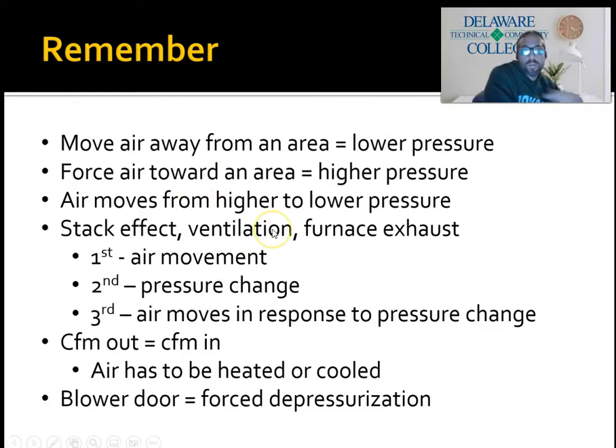But you can change pressure with a furnace, which is removing air out of a building. An exhaust fan, even a laundry fan, will change the pressure in a building. And just remember, as an absolute rule, that for every cubic foot per minute that goes out of a building, a cubic foot per minute comes back in, and vice versa. So if I'm bringing in 500 cubic feet per minute with a ventilation fan, then I'm ejecting 500 cubic feet per minute as well. And then we talked a little bit about a blower door. It depressurizes a house or a building on purpose, so you can pick up on all the various small leaks in the building.